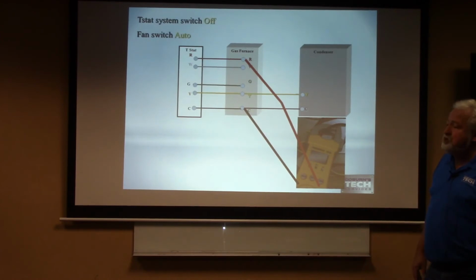All right, so let's use our meter. What would I read across R and C if my transformer was in that gas furnace right there? 24 volts. Good. Your thermostat switch is off and the fan switch is in the auto position. Would I still read 24 volts? Absolutely. All right, let's switch it to cool. Your fan switch is in the auto position. R and C, what should I read? 24. That's where my voltage is being generated. Absolutely. So now I'm going to shift down to the W. What should I read across W and C if it's in the cooling mode and in the auto?